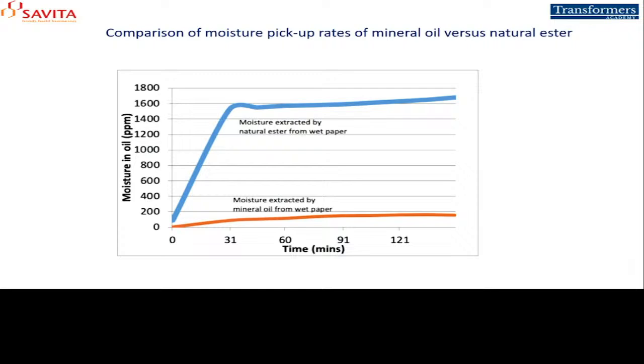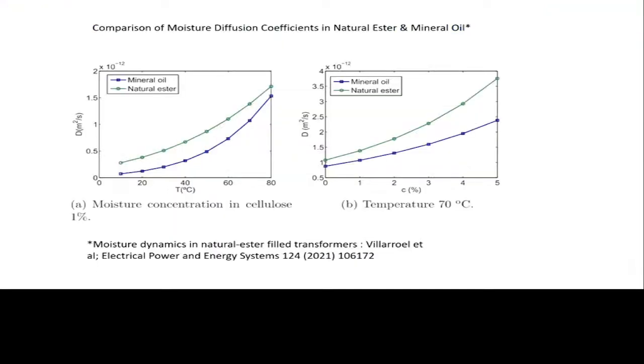Now, this is an interesting graph where, in our laboratory, we wetted the paper. That is, paper was saturated with moisture, and then we tried to see how much of that moisture one can extract using mineral oil in one case and ester oil in another case. The top one is a curve for natural ester, and you can see the moisture in paper is completely removed within 30 minutes. Whereas for mineral oil, the lower curve, the extraction rate is very small. The total extracted amount is also very small. So this is the most important difference in chemistry between the two.